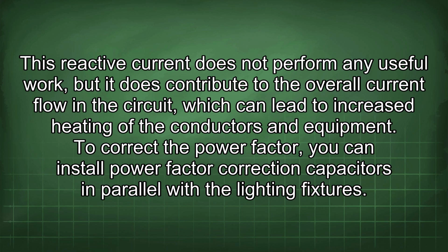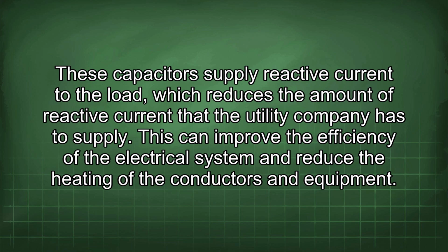To correct the power factor, you can install power factor correction capacitors in parallel with the lighting fixtures. These capacitors supply reactive current to the load, which reduces the amount of reactive current that the utility company has to supply. This can improve the efficiency of the electrical system and reduce the heating of the conductors and equipment.